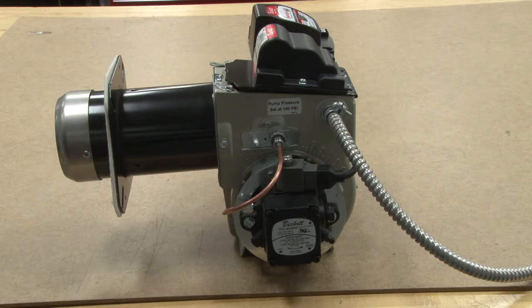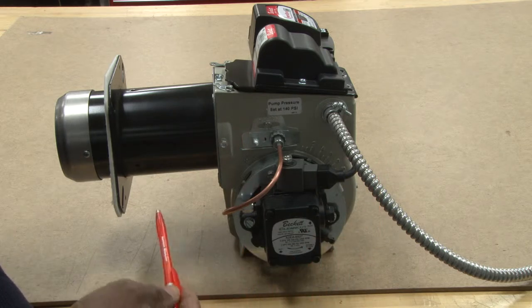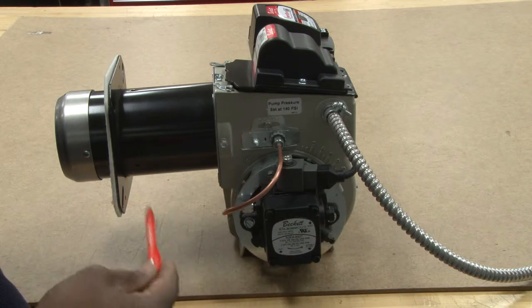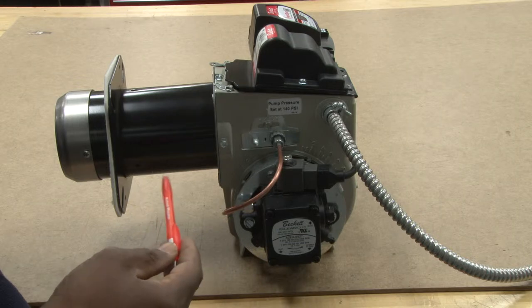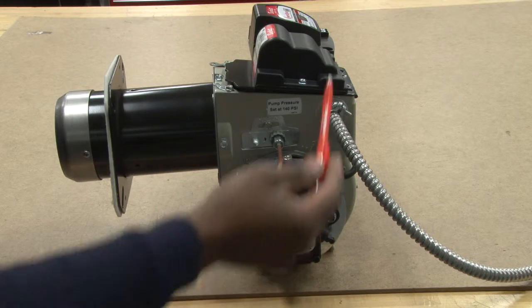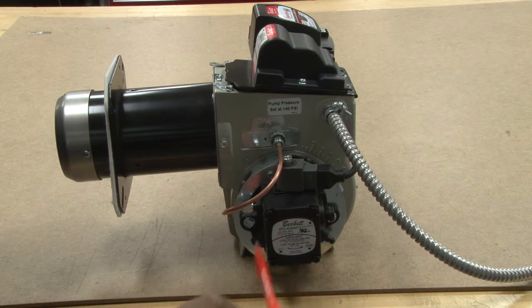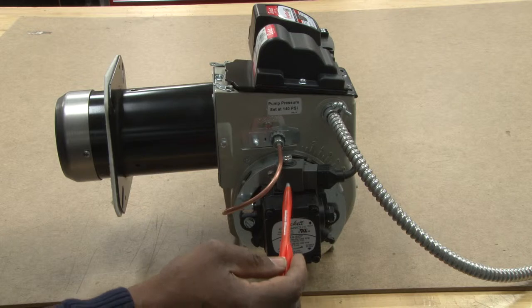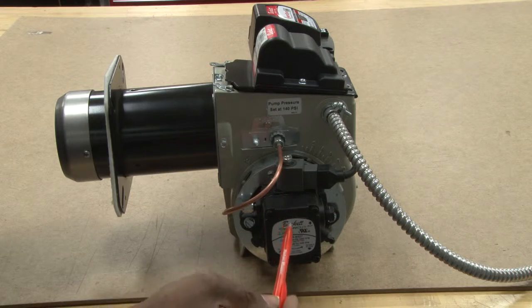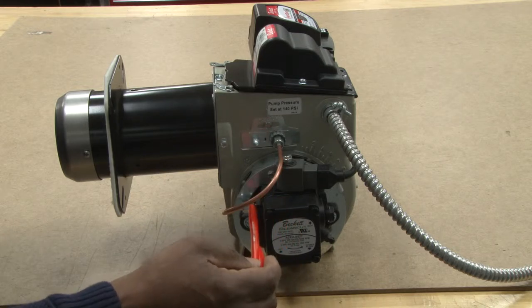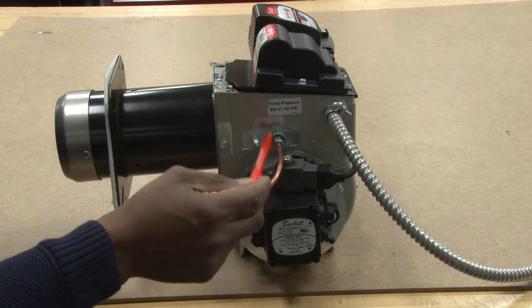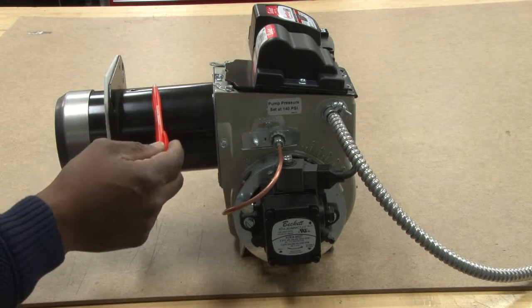In this video, we're going to discuss oil burners, how they operate, and the components of an oil burner. This is the assembly of an oil burner that has been removed from the furnace itself to show you the components that you will find. Just the external portions of it, we have in front of it the oil pump. This pump is designed to generate about 100 psi of oil pressure at the discharge to go to the nozzle that's on the inside of the burner tube.